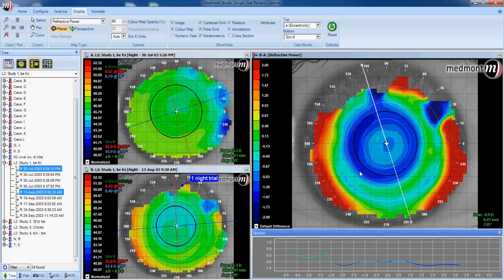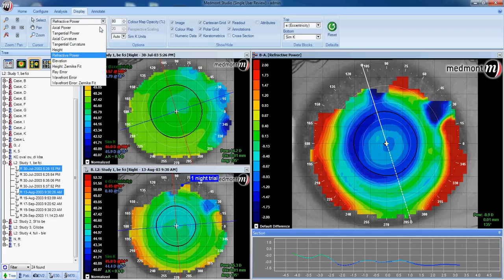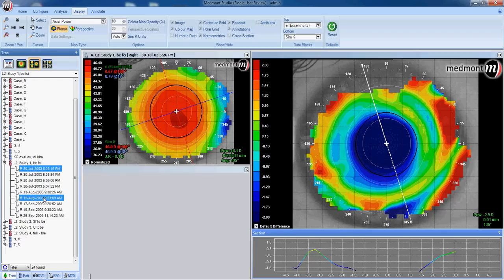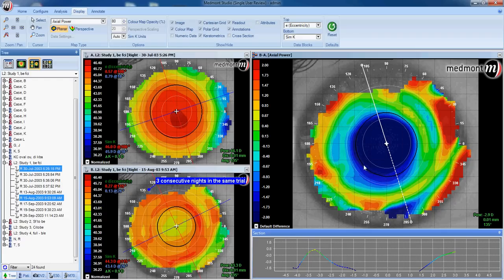The refractive power map looks very similar to the axial subtraction map in the position of the treatment zone and the refractive change. You can also look at the refractive power map with the post-treatment exam alone to determine if the effect appears fairly spherical — whether you are sphericalizing the pupillary zone, pushing astigmatism out of the way, and placing the treatment zone where you would like it. Going back to an axial map, we can observe this patient after three consecutive nights of wear by unselecting the one-day map and selecting the three-day map. Our axial map now shows a treatment zone filling in nicely — we are up to 2.9 diopters of refractive change. This concludes video nine on the practice of orthokeratology with your Medmont E300 corneal topographer.